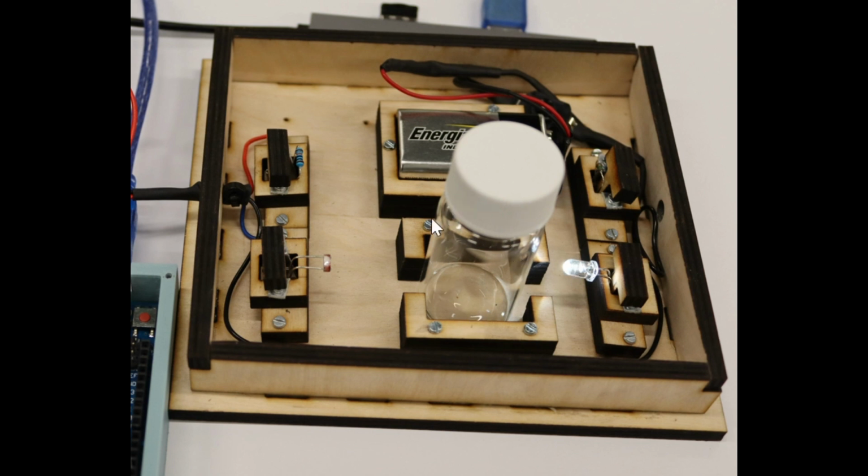At some point, we will measure the compartment itself, meaning the sample holder itself. On the other side, we have a photodetector, the sensor which detects light. The light that is transmitted is what we're going to take care of. Light that emerges from this side goes through the sample and is received on the other side. That is transmission, the principle we're going to use. That's why we have ignored all the others.